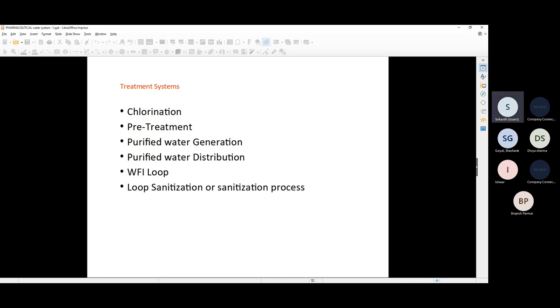The outlet of RO EDI is considered purified water. Once it reaches the set parameters - conductivity, pH, and TOC within limit - we design the generation system based on the raw water and what is required at the end. The user will write specifications stating what treatment this water requires and what purified water generation is needed.